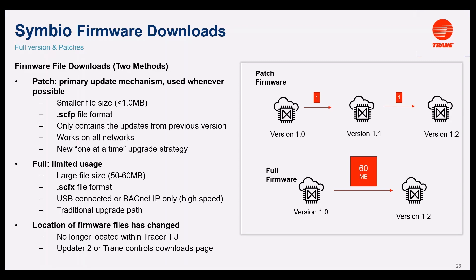The idea with these patches is that you can use them through all the networks — for example, BACnet MSTP or RS485. The idea here is that you are going from one version to another, one by one. You can go from version 1.0 to version 1.1 with one patch, and then with another patch go from version 1.1 to version 1.2.